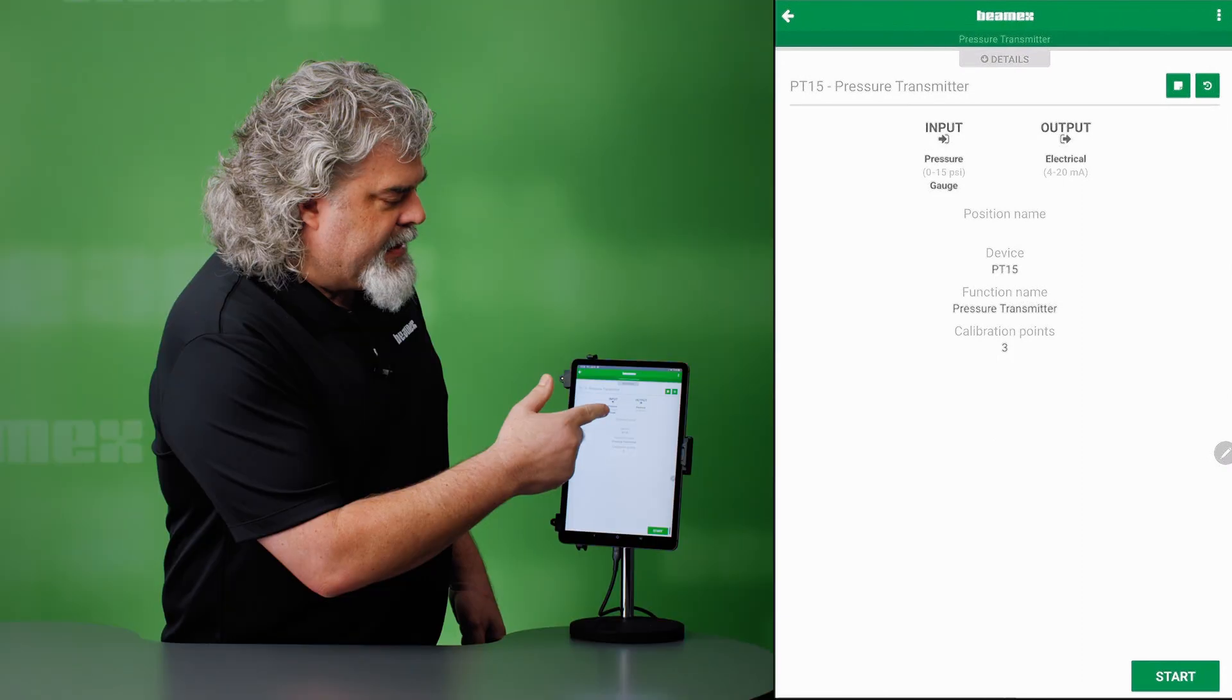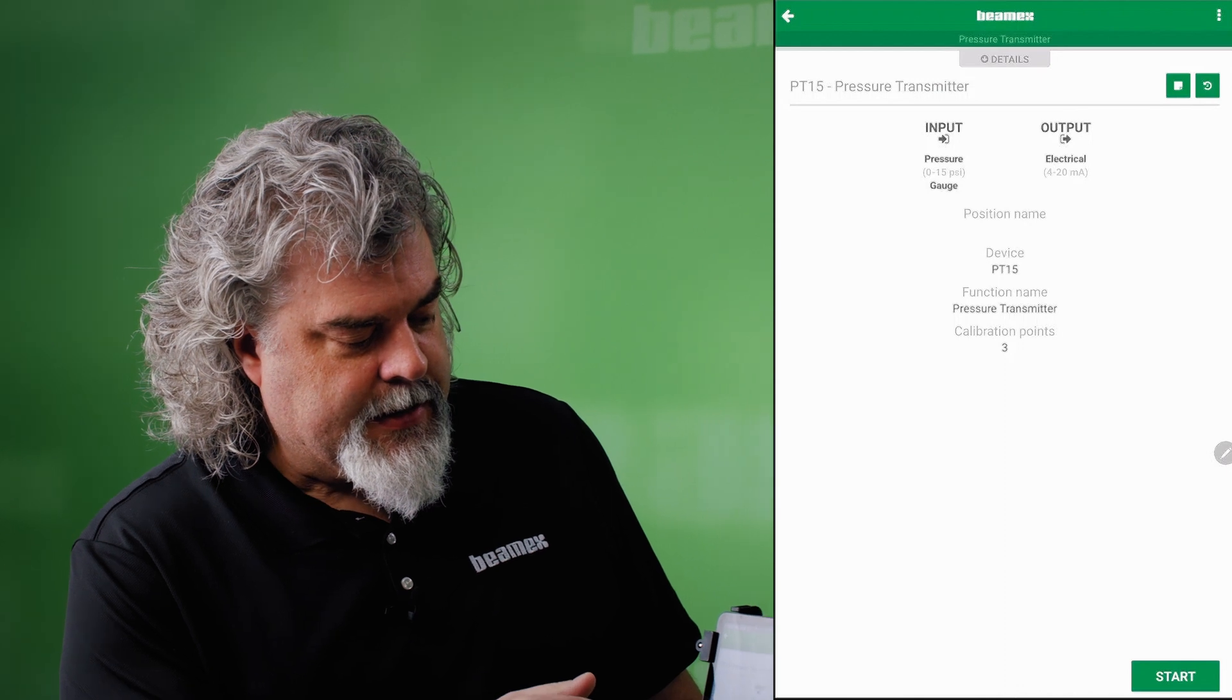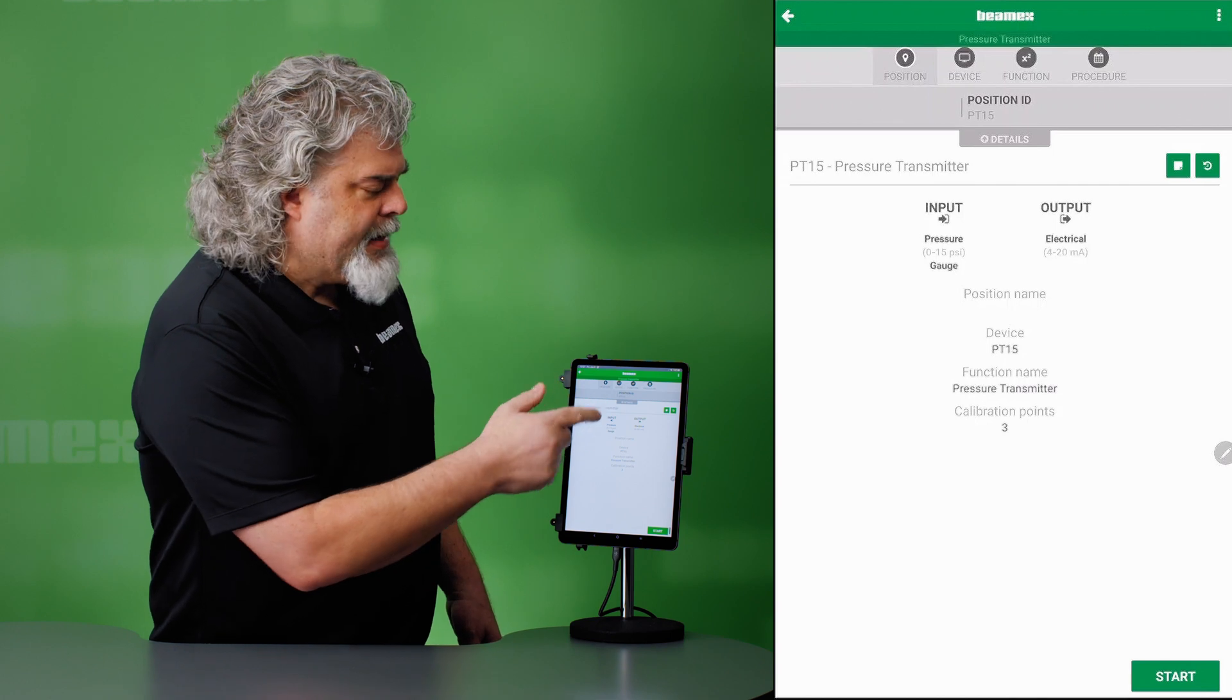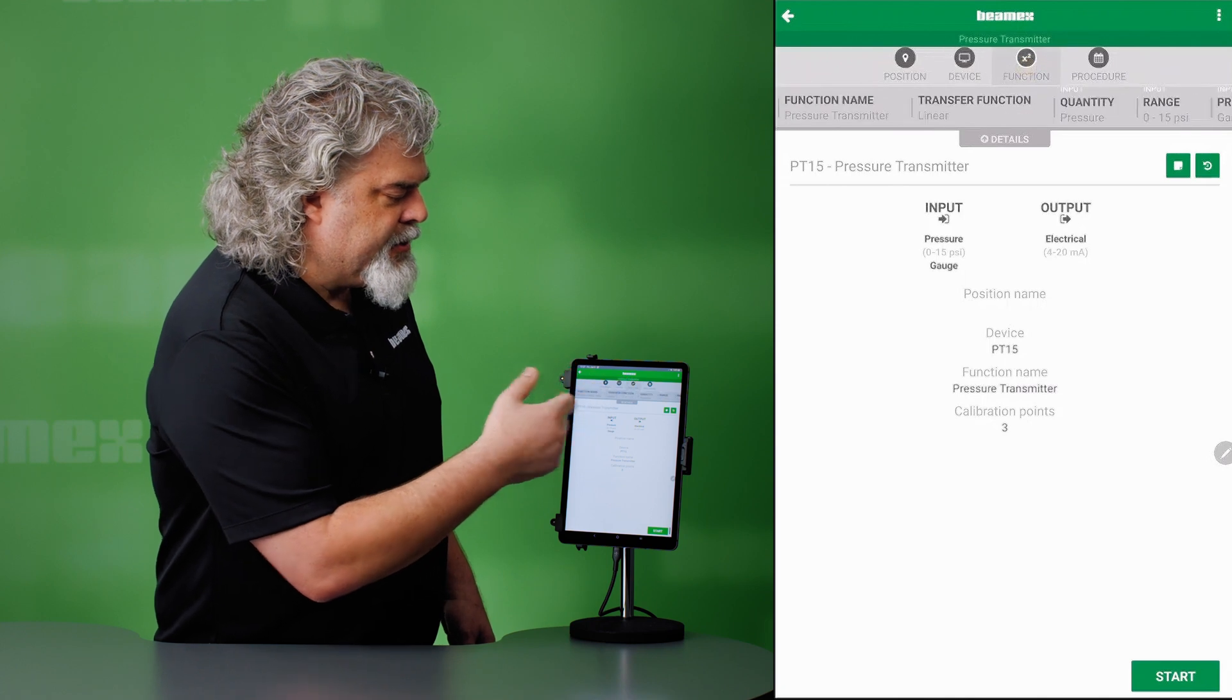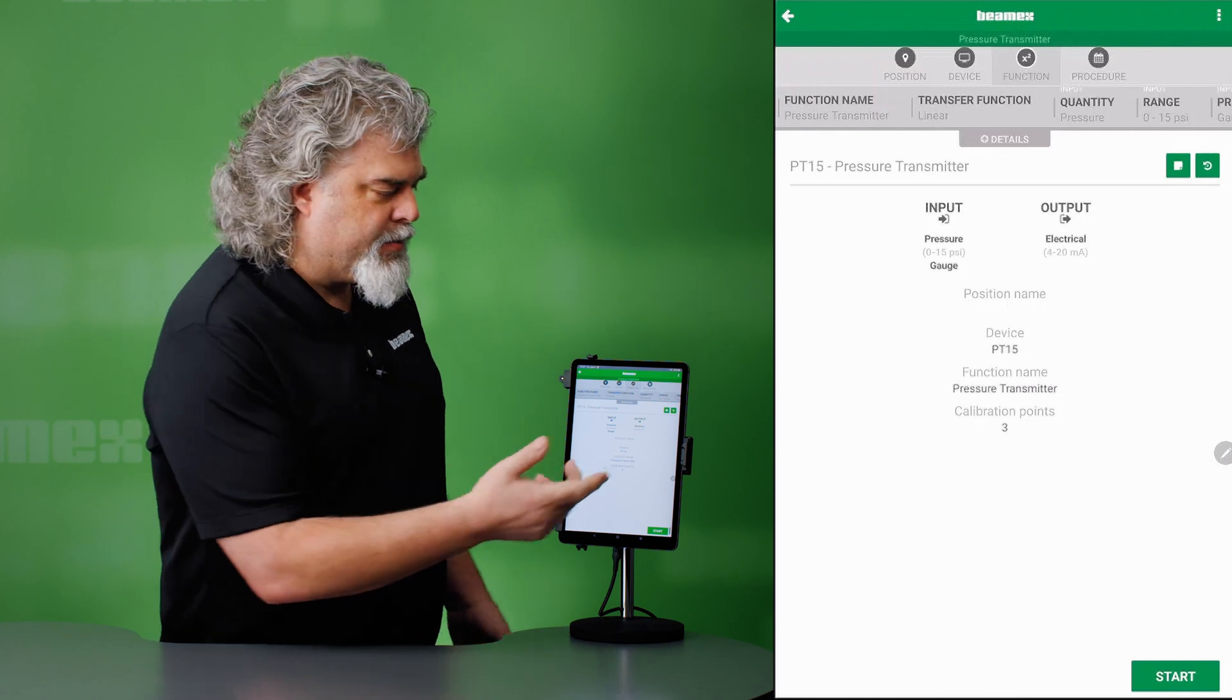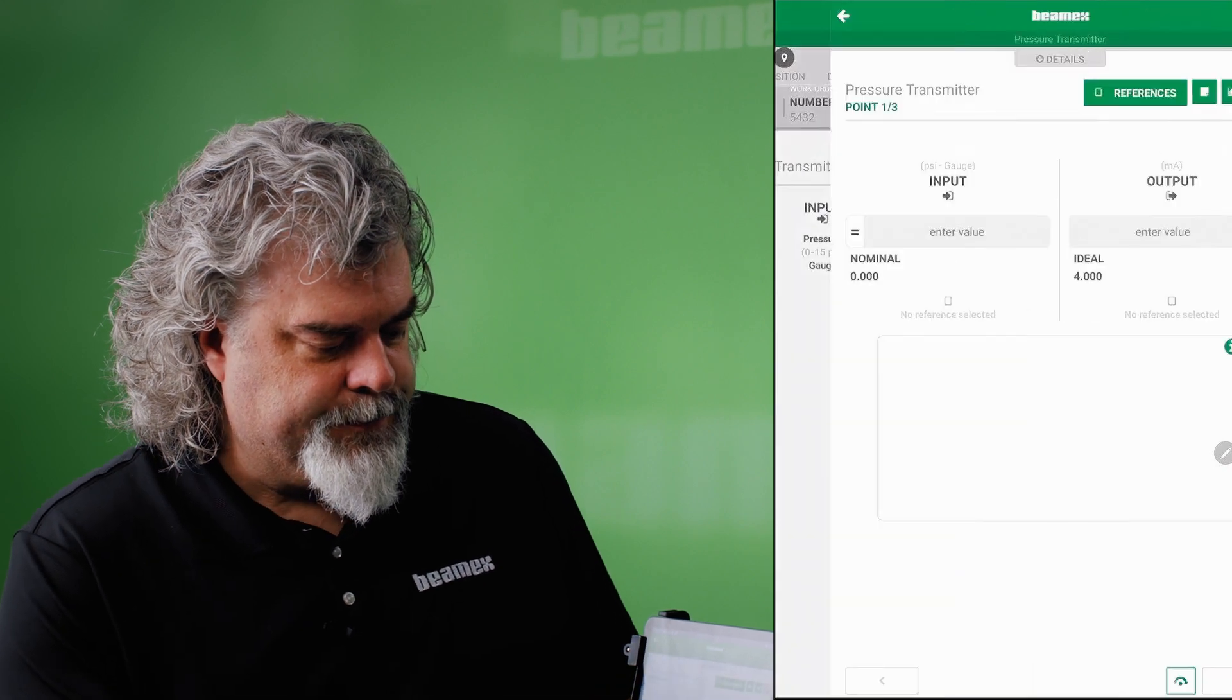Input is 0 to 15 psi. The output is 4 to 20 milliamps. We have three calibration points. More details. The first is a position, you might call this the tag or the tag name, tag ID. There's device information, then there's function. This describes what it is that you're testing. If it were a switch, it would have different parameters. And finally, the procedure itself. So let's get to it. Let's hit start.